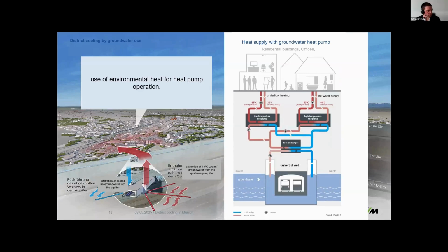As I said, we not only use the system for cooling, but also for heating. So mainly we install the system for cooling, and in addition to that, we install heat pumps at the customer's building. So we can use the system in 2 ways. And also there's a need to equalize the temperature in the ground, because if we are allowed to use the groundwater, it is used not only for cooling, but for heating. So the groundwater will have around the same temperature as we took it out before.